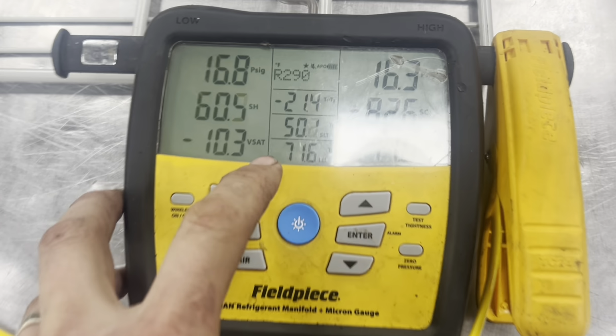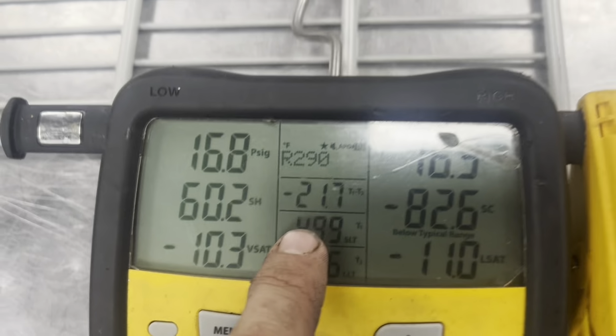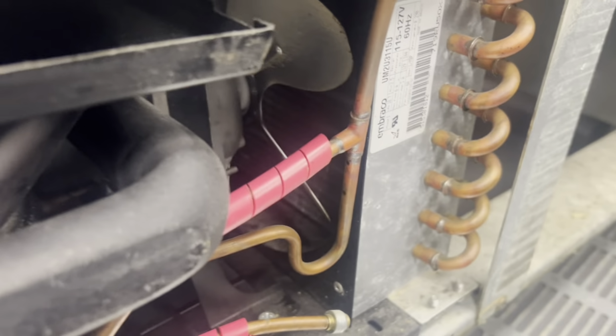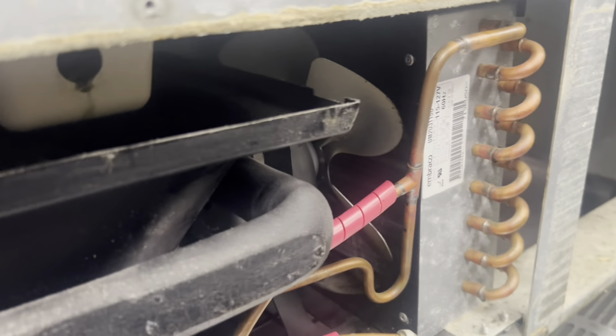There's a lot going on. So this is the only thing we're looking at. None of this is real. The only thing that's real is this temperature probe that's in there hanging, and it's playing catch up. So I don't know what temperature it really is inside yet, but we've satisfied and shut down. He said the problem is this unit always was hanging out right at the north end of OK. It was always 41, 42, 44.